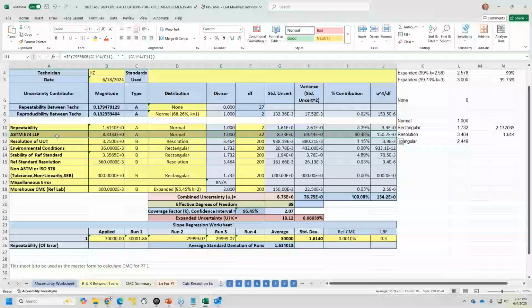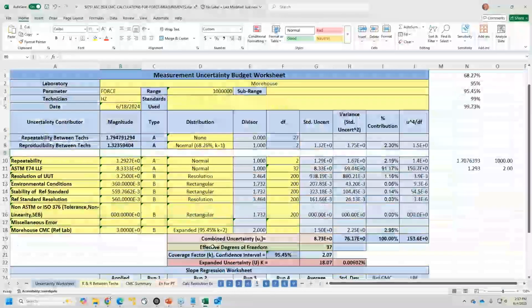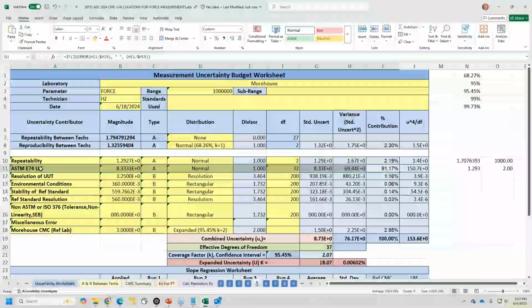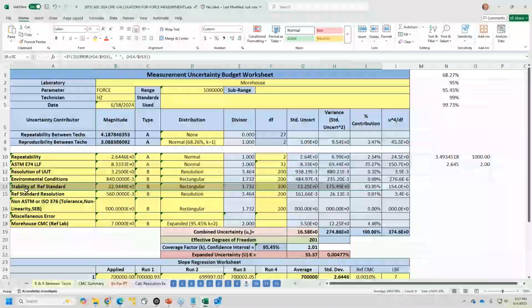If I wanted to attack anything, I would look into maybe a second range on the load cell. I might look into a different load cell for something lower than 30,000 pounds. But if we look at this E74, if we start going to say 300,000 pounds, E74 is dominant. Look at, I go to 700,000 pounds. Look what happened. The stability of my reference is 63.85%. The ASTM E74 lower limit factor is no longer dominant.